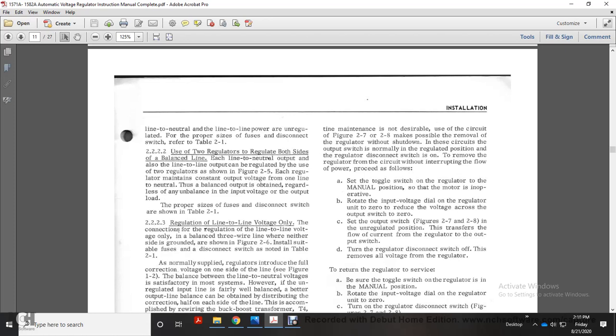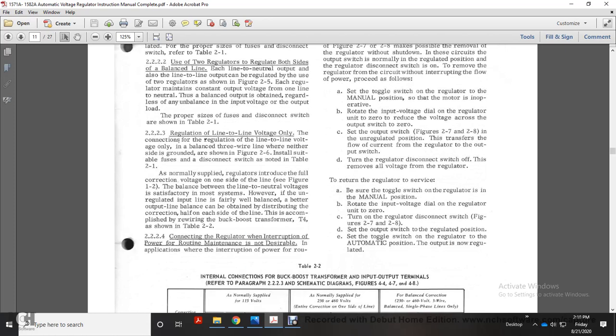This removes all voltage from the regulator. To return the regulator to service, the toggle switch of the regulator switches in the manual position. Rotate the input voltage dial on the regulator unit until 0. Turn on the regulator disconnect switch. Figure 2.7 to 2.8. Set the output switch for the regulated position. Set the toggle switch for the regulator to the automatic position. The output is now regulated.